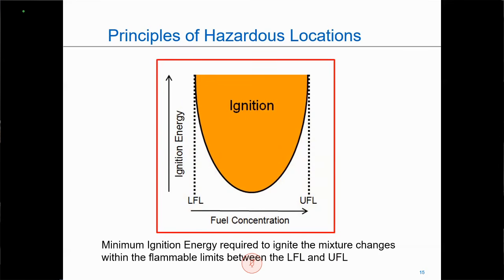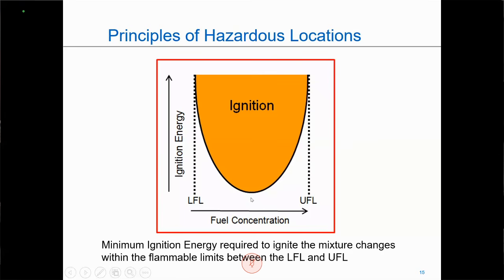Now, when I'm looking at the upper and lower flammable limits, depending on the percentage, it can affect the maximum explosion that you can have for that particular type of gas. When you're in the exact middle, it's going to be the optimum for the largest explosion that that particular gas or vapor can produce. The closer you get to the lower flammable limit or the upper flammable limit, it's going to weaken that explosion to a certain degree, and it'll also take more energy to ignite that particular gas. But don't make the mistake of thinking this is comforting, because a weakened explosion is still an explosion and can still injure and kill.